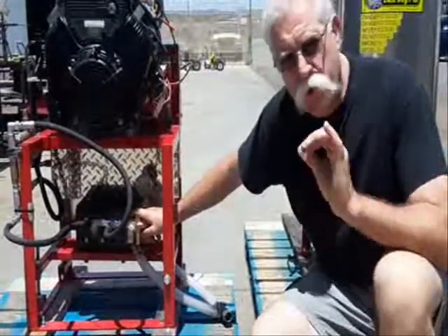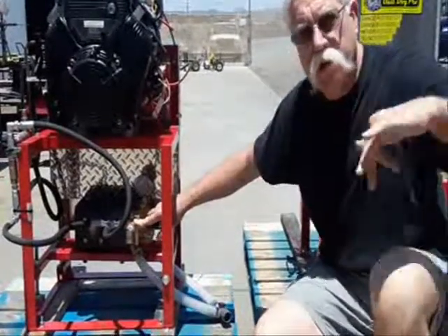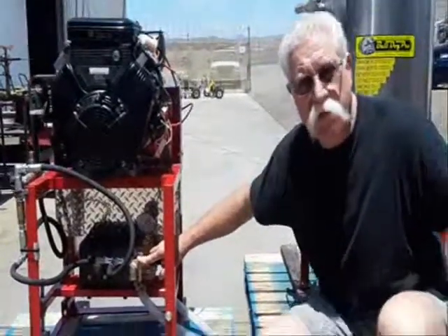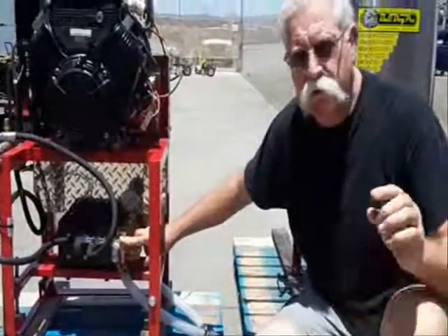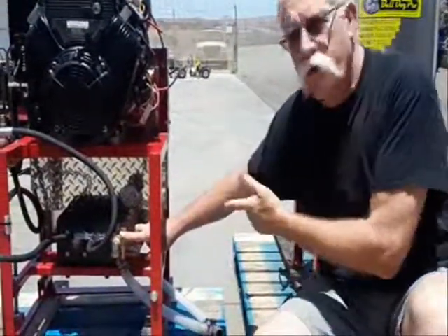This is a pressure trapping type unloader. It traps the pressure in the outlet side of the unloader and everything after the unloader. So if there's any leaks in your hose reel or quick couplers, or if the gun is bleeding, your unloader is going to think that the gun opened again and it tries to repressurize. That's not good for the system. It's cycling it more than it needs to be cycled.